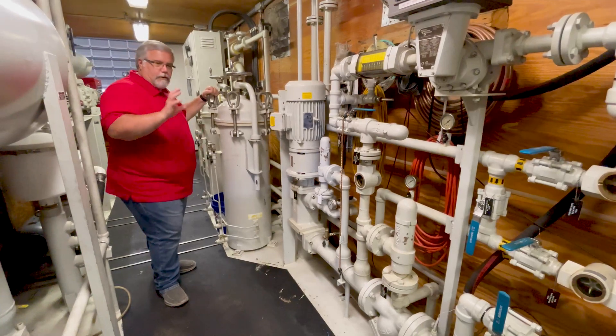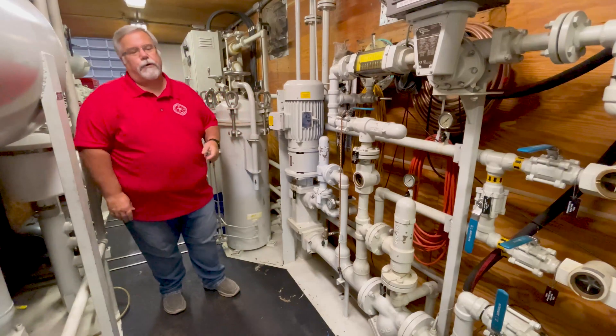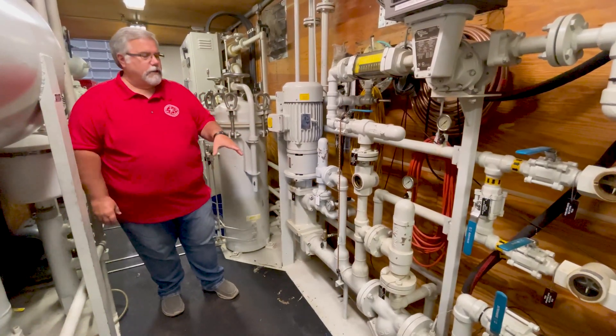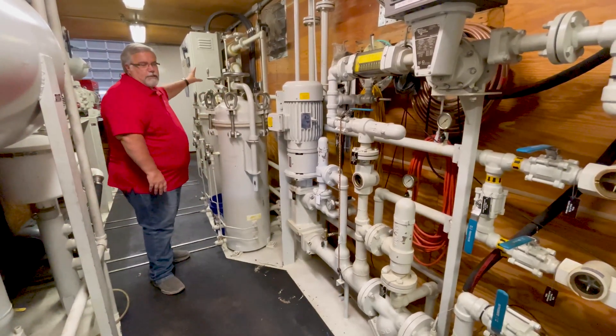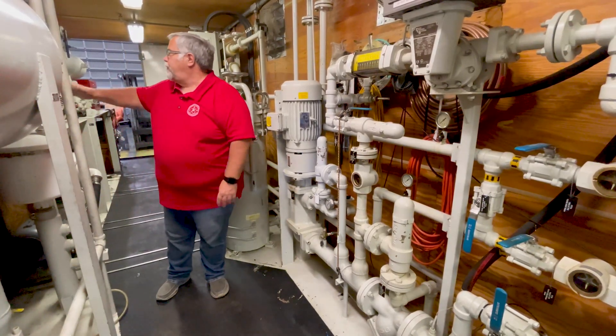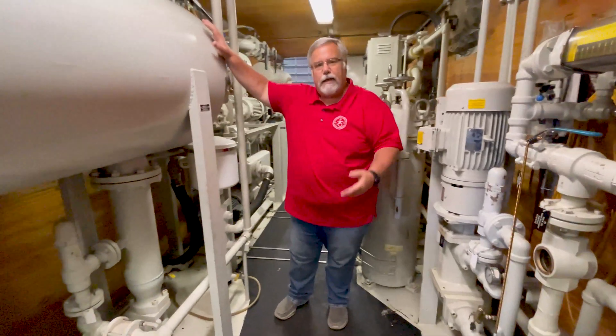They're going to drag a hose to the bottom and to the top of the transformer. They take the dirty oil out of the bottom, it comes through this system — through some pre-filters, through a heat system where the oil gets heated up — and then it goes into a vacuum chamber, right here, and then into some Fuller's Earth tanks.